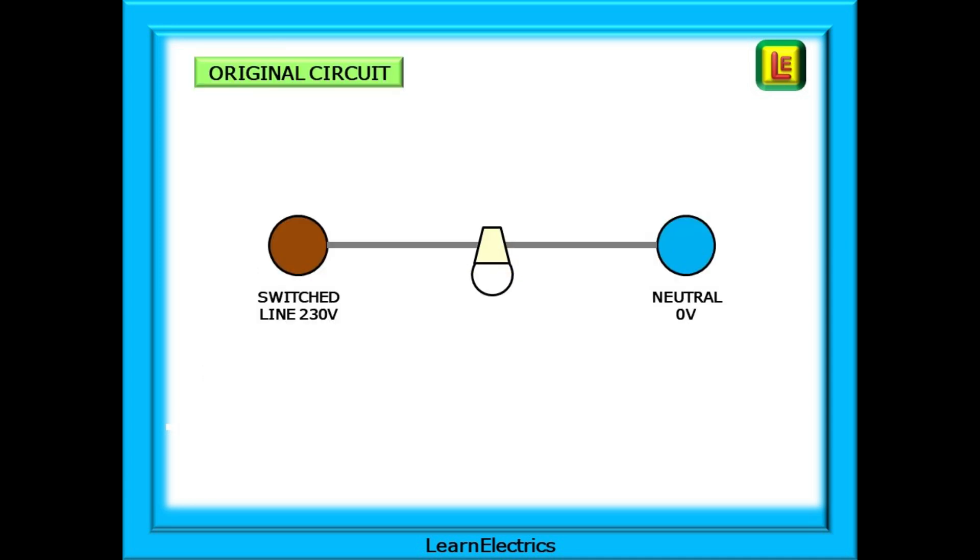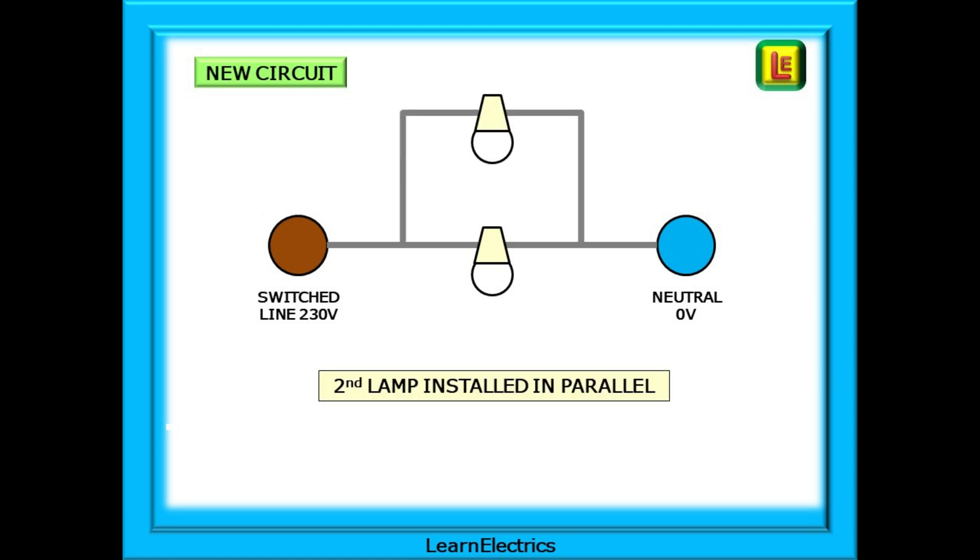What is it that we want to achieve? At the moment we have the 230 volt switched line connecting to the lamp and from the lamp to the neutral. When 230 volts appears at the switched line the lamp will come on. To make a parallel lighting circuit so that both lamps come on at the same time, we need the switched line to be connected at the same point on both lamps and the neutral to be connected to the same point on both. Any voltage on the switched line is the same voltage on both lamps.